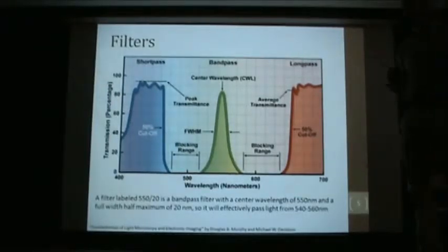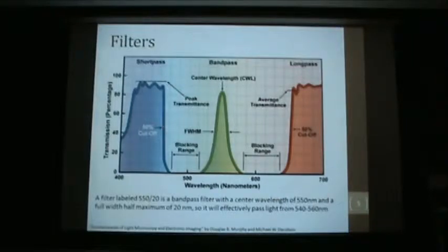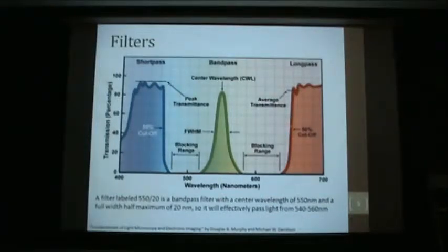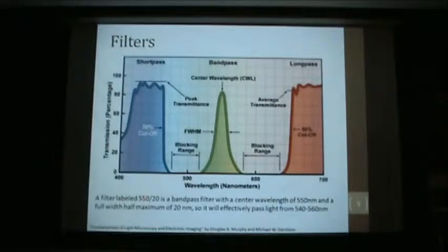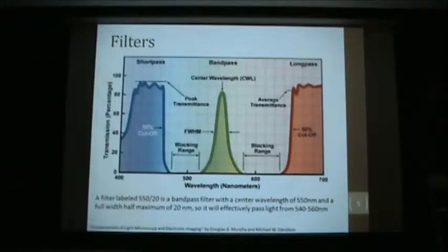There are a couple of different kinds of filters. A short-pass filter will pass all wavelengths shorter than that number — so this is probably a 450 nanometer short-pass filter, passing things 450 nanometers or less. A long-pass filter is just the opposite — it passes light at longer wavelengths, so this is a 650 nanometer long-pass filter. A band-pass filter will pass just a specific band. The nomenclature is the center wavelength and the full-width half-maximum. So a 550/20 filter passes light from 540 to 560 nanometers.